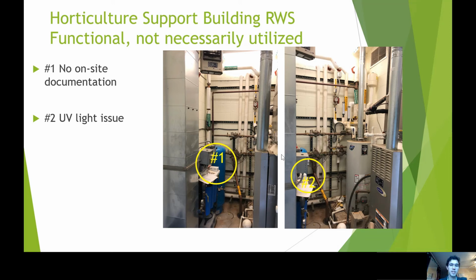An additional point I'd like to make here is that the UV reactor is plugged into an old outlet with a light switch. So if you turn the unlabeled light switch off and on, you actually turn the UV light on and off, which is definitely a problem.